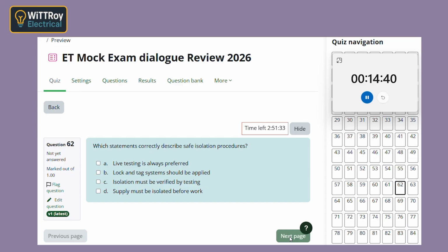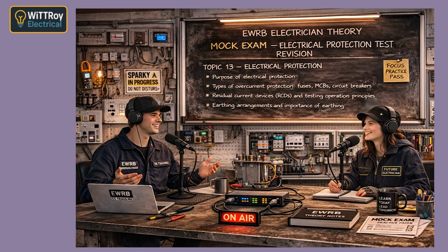Exactly. Then lock and tag. Locking prevents accidental re-energization. Tagging warns others that work is being carried out and the circuit must not be restored. So live testing is always preferred is wrong because safe isolation is the normal safe approach before work. Correct. Live work is not the preferred default. Safe isolation is. Yeah, this section really does need more explanation.